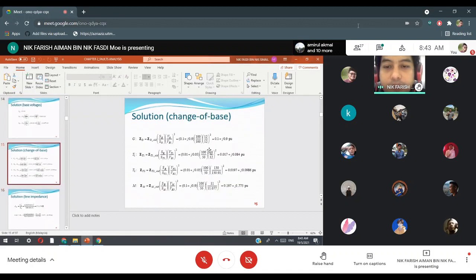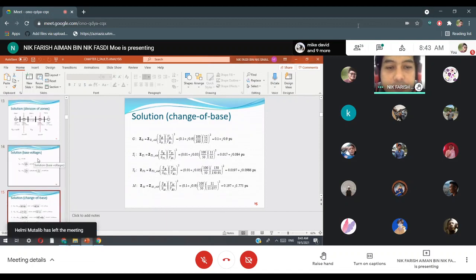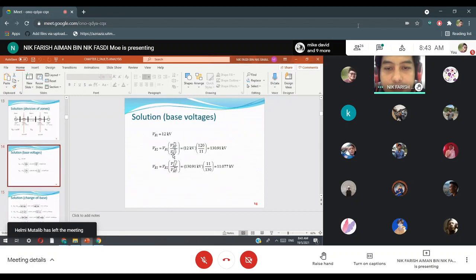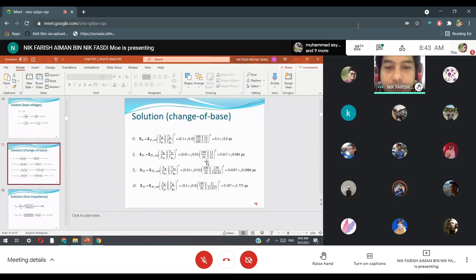And then V transformer 1, 11 divided by base 1, which is the base we calculated earlier - this one, V base 2, base 3. So just substitute into the formula and there you have T1's per unit impedance.